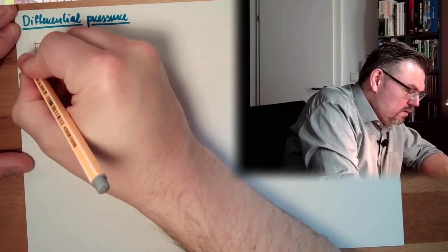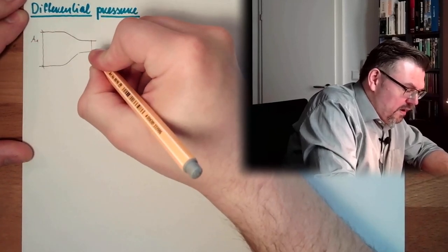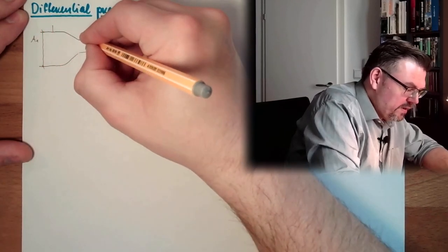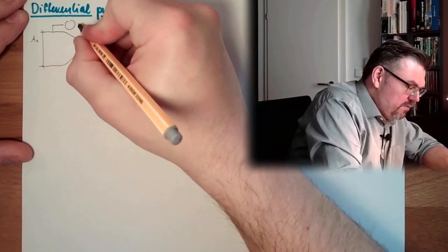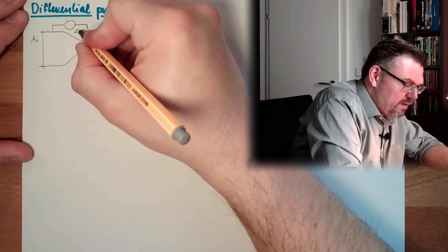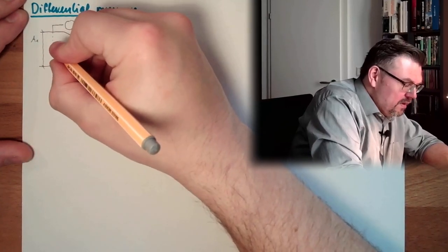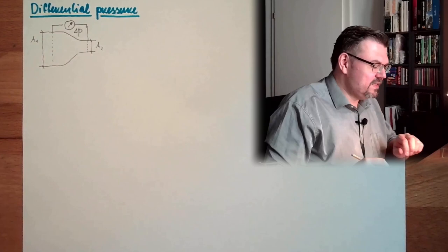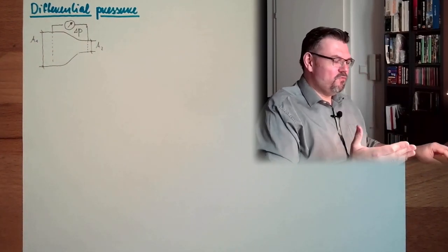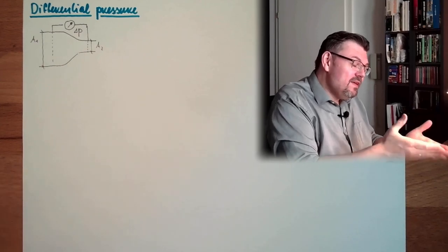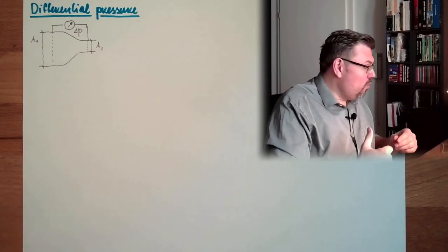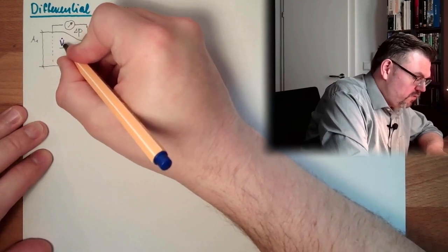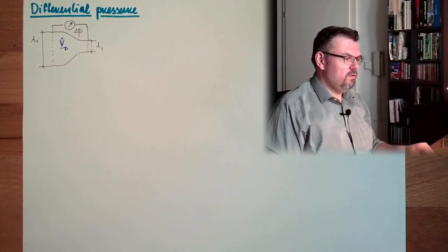We have here an A1, area 1, and here we have an area 2 size. And what I am actually measuring is the pressure difference between those two things. So I am measuring the delta P between this position and this position. And how does it work that I can realize from this delta P to the flow? Because actually what I want to know is the volume change per time point.